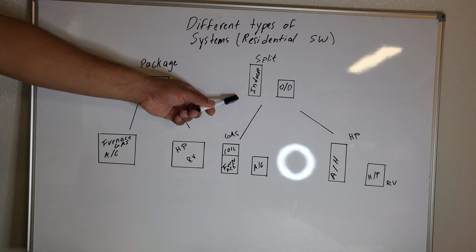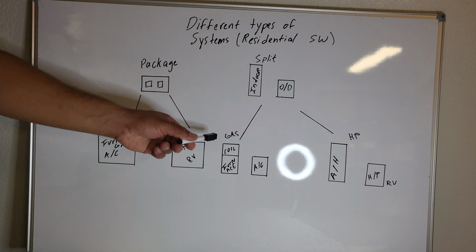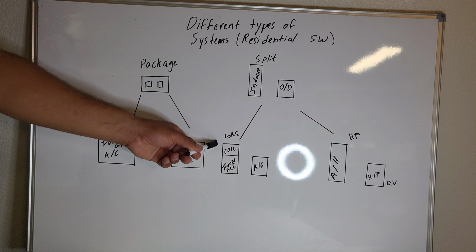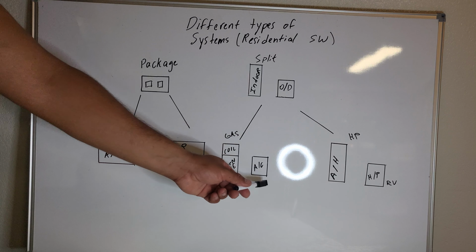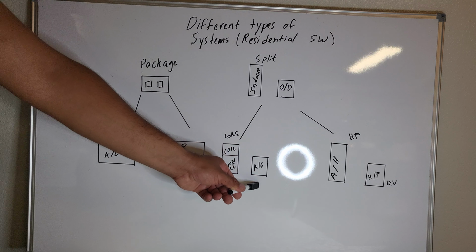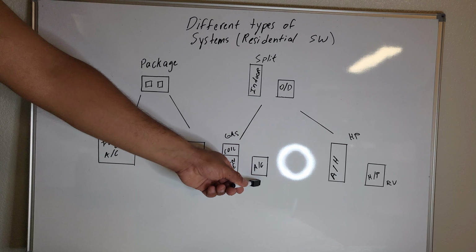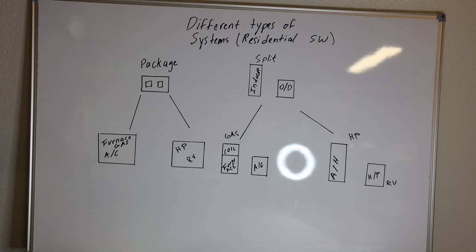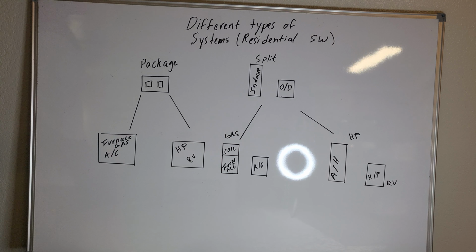The split unit will be broken down again primarily into 2 different sections. You will either have a split gas, which has a furnace and a coil that sits on top of it, or sideways if it's in an attic or whatever, right? And an air conditioner or a condenser outside. This is actually legitimately a condenser because it is condensing every time it's running. So that's the only legitimate time you can call it a condenser, even though some folks call any outdoor unit the condenser, but that's just not accurate, okay?